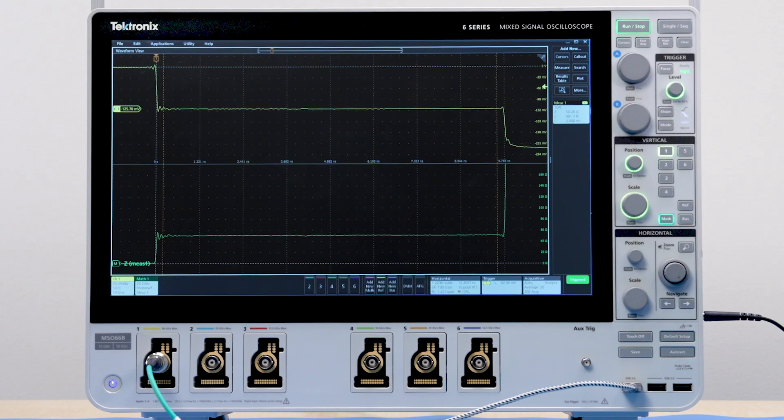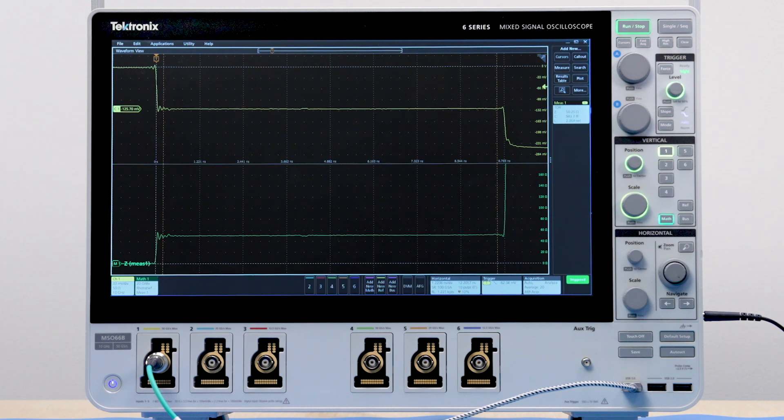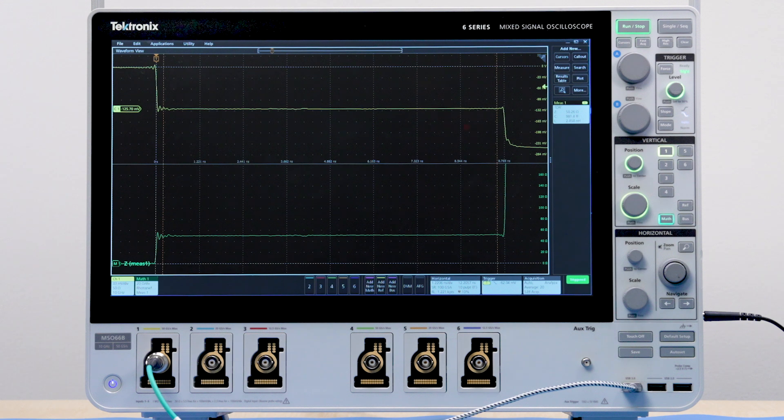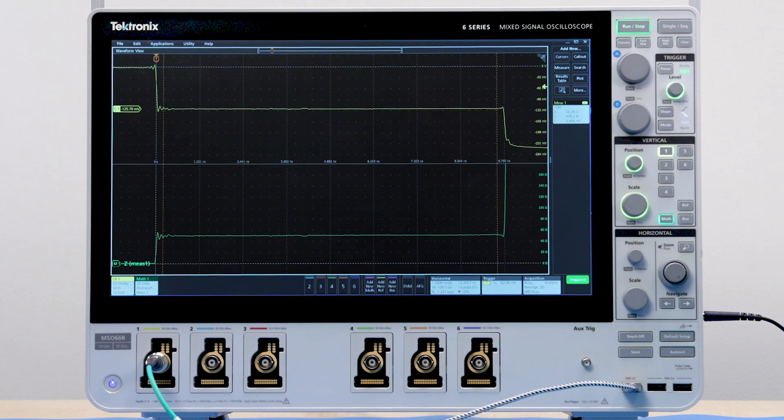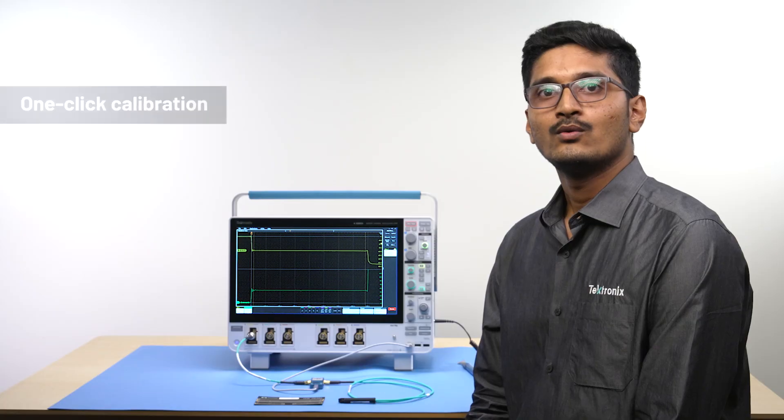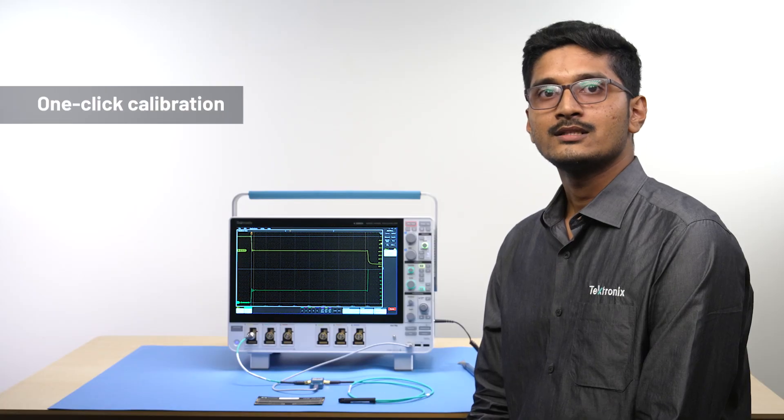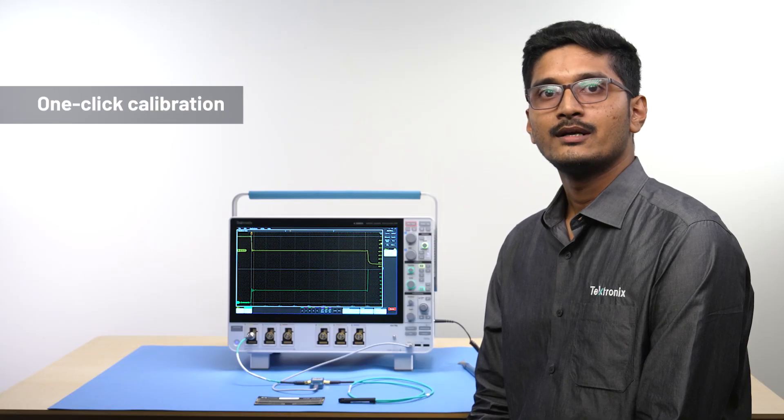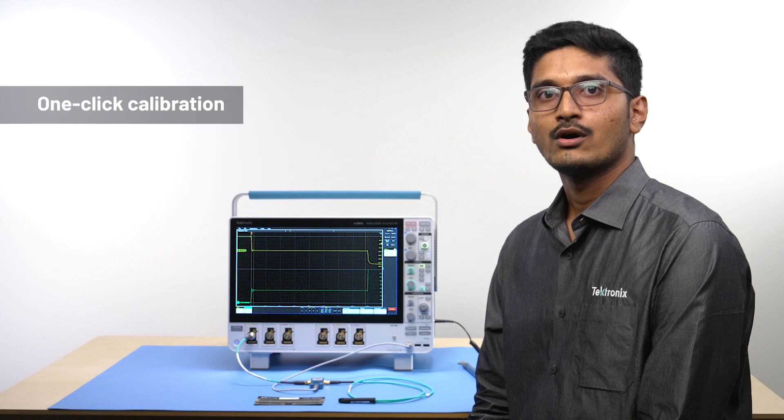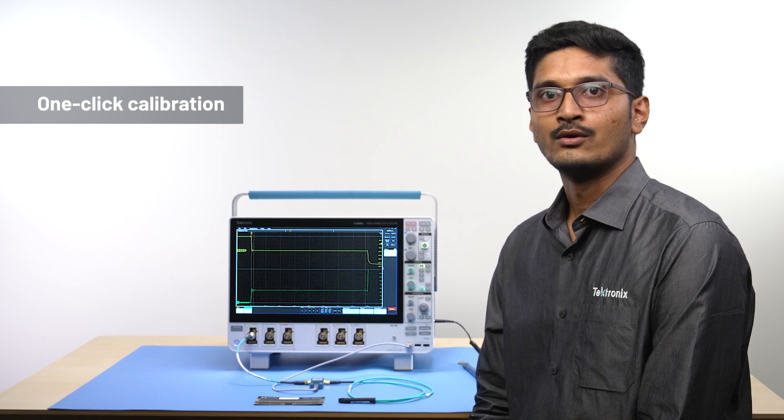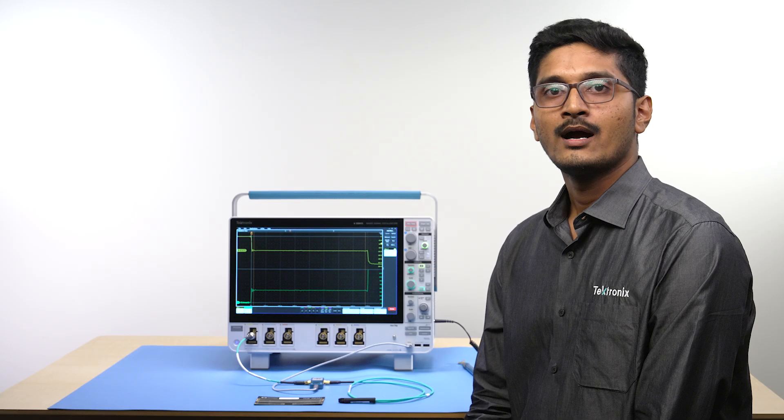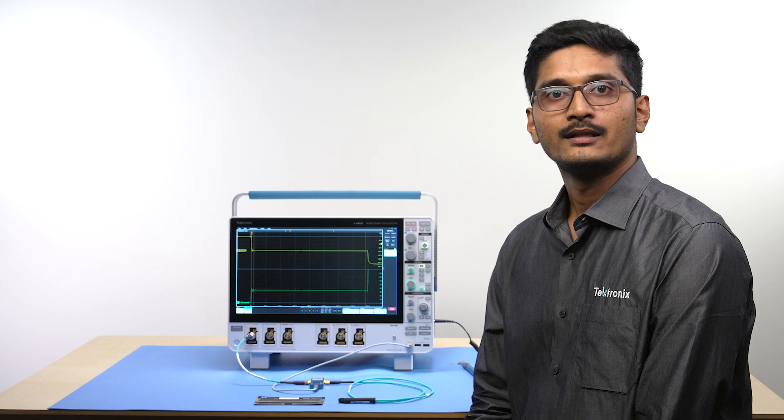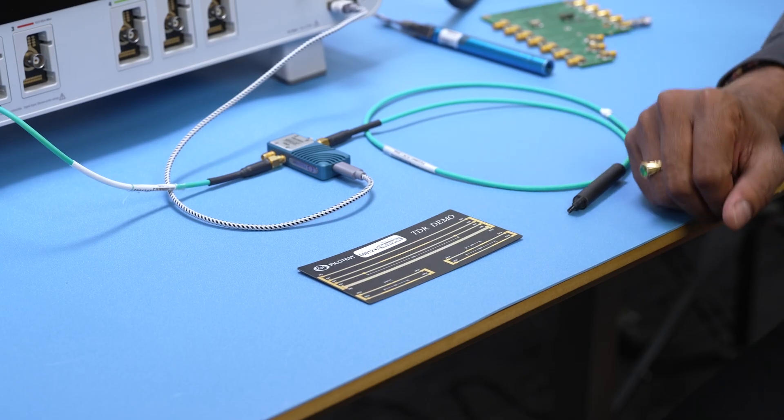During the preset operation, the software automatically measures the low level, high level and the step amplitudes of the signal and decides compensation factors for the raw waveform and also adjusts the signal accordingly. With one click, the system is calibrated for an open, short and load using the single waveform. Now I am ready to make the TDR measurements on my DUT.